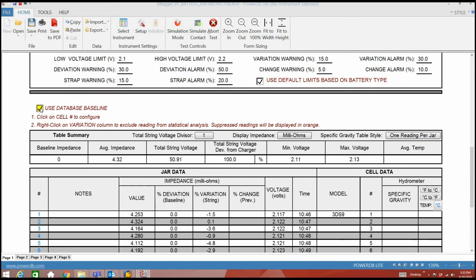Now, if I don't know the baseline value, then I simply click on Use this test as baseline, and the software will automatically calculate the baseline value. The baseline value will be used as a reference value for analysis for all following tests on this string. So you're only going to need to do this once. If I have programmed a baseline value into my test equipment, I can select Use Instrument Baseline Value. The software will then use the baseline value that was programmed into the unit during testing.